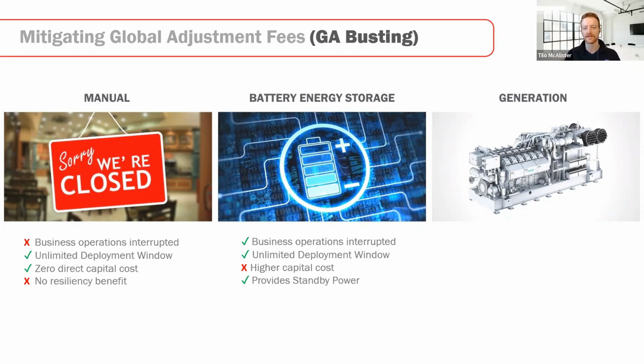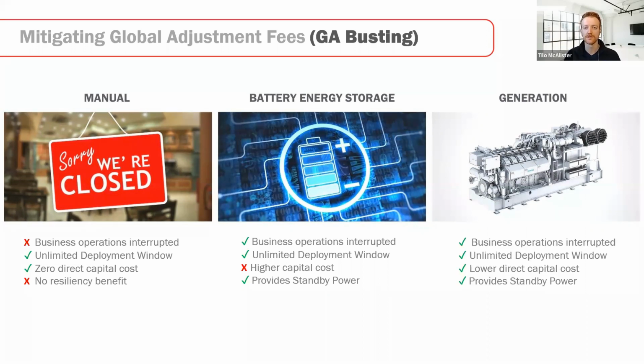We've seen this with customers that install batteries: they miss a peak because they ran out of battery capacity before the peak actually ended up occurring, and you don't know until after the fact when the peak occurred. The other benefit of batteries, though, is that if configured correctly, they can provide emergency standby power for at least a short duration to the facility, which is a significant benefit as well.